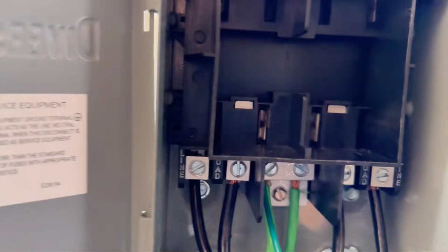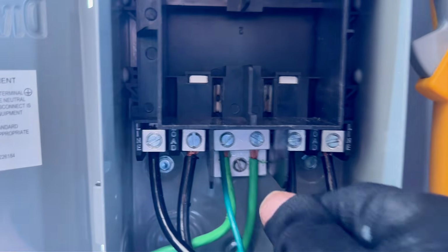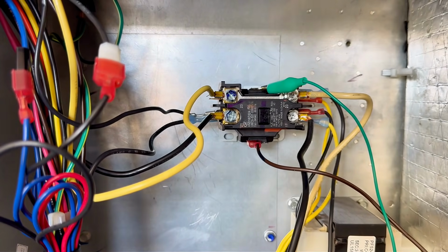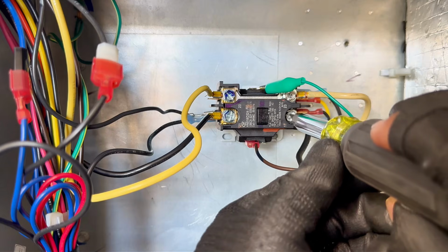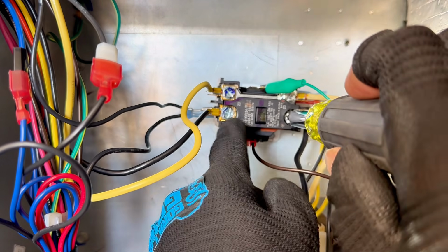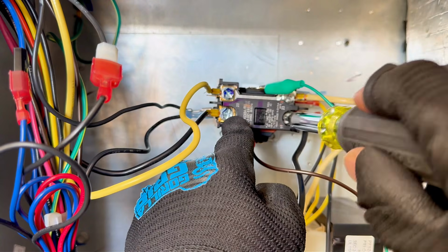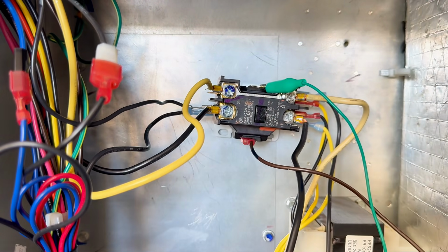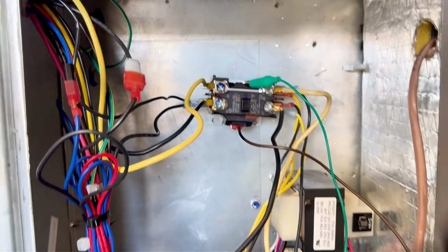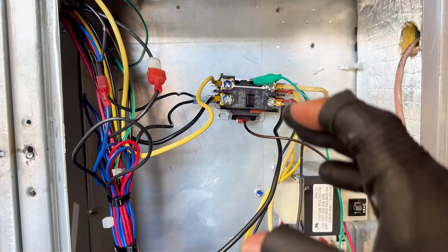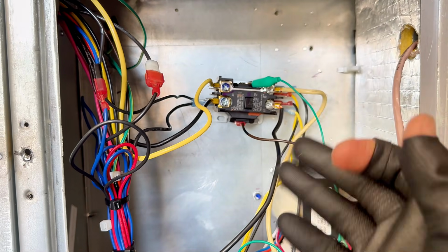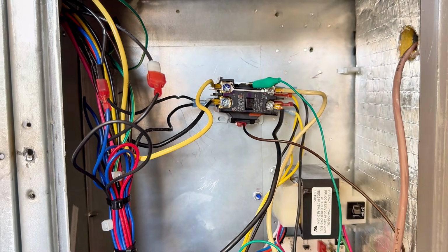And then I always do the little pull test, you see, not going anywhere. And then on this one here too, right? Any parts, even with low voltage, you're gonna check that everything has a good connection, you see? Okay, and then tight, okay, and that's it. That's all you gotta do. And like I said, this is part of maintenance. When you go to jobs, just make sure that everything's tight. Like that, you can prevent the wires from overheating and possibly other issues.